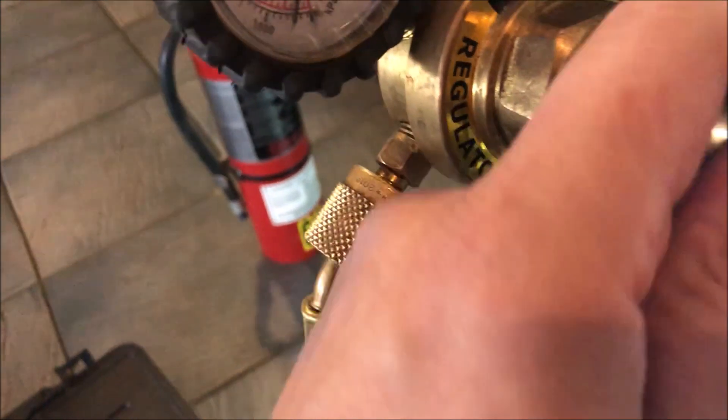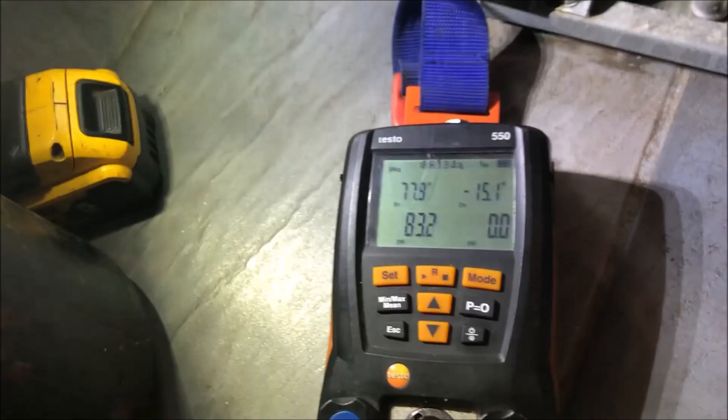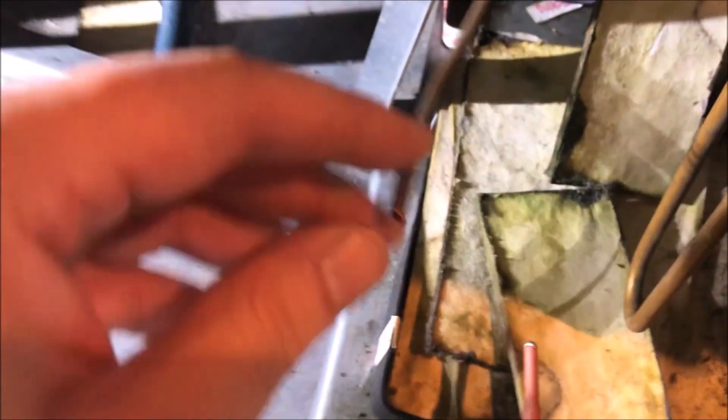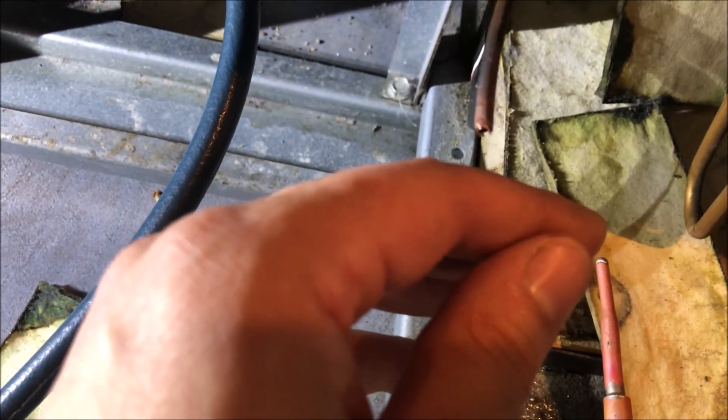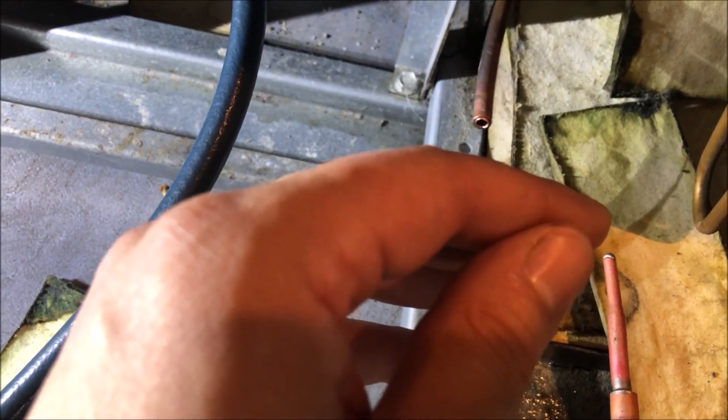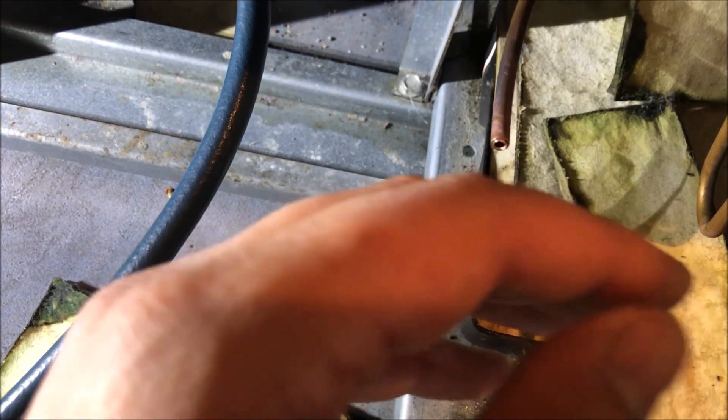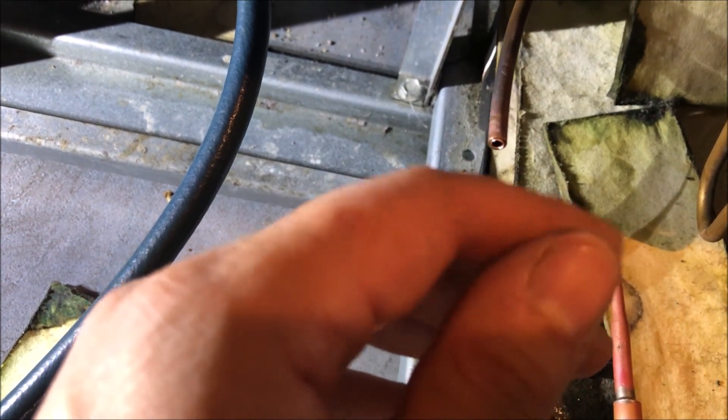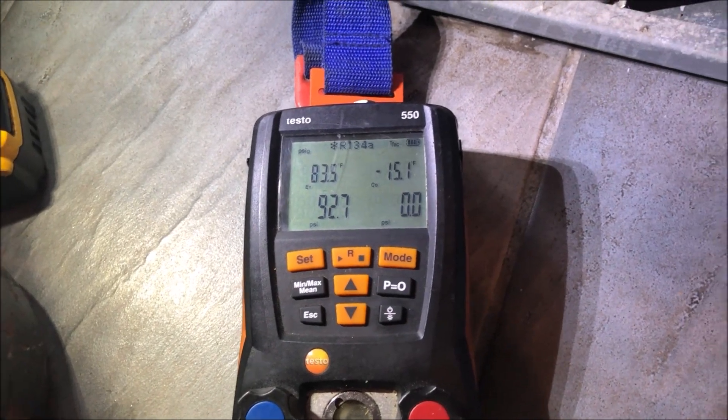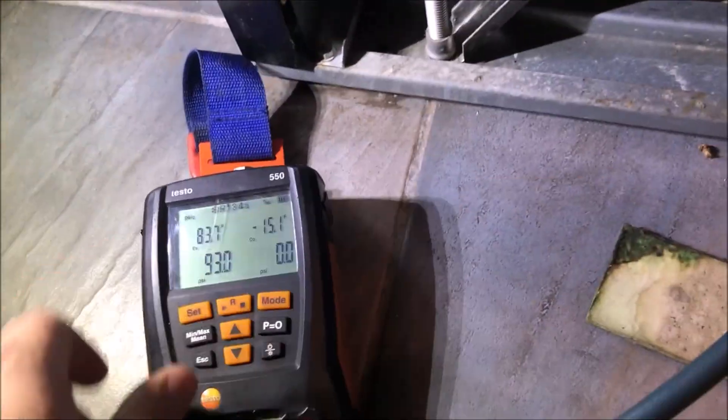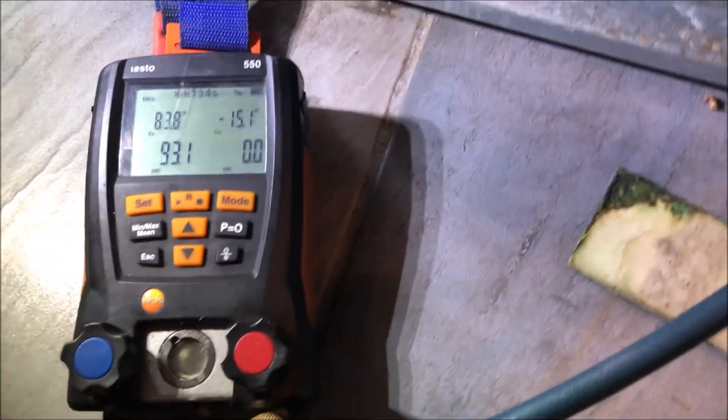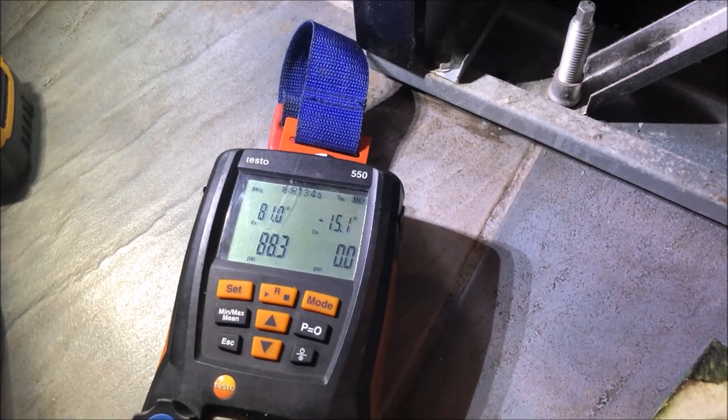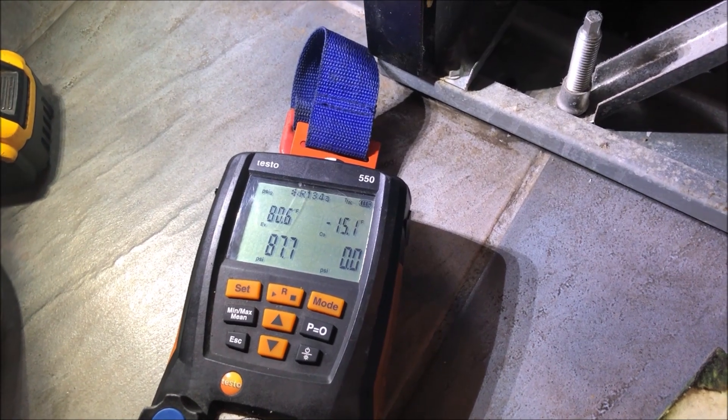So let's just keep pushing some nitrogen through. We're still not out of the woods here because what we want to do is we want to test the pressure coming through at our operating pressures. Just because we have it flowing through at 83 PSI right now doesn't mean that it's going to be flowing through where we're at our 14, 13, or 12 PSI. I'm going to continue to blow it through. Let's get a little bit higher here. We're up to 93. So what I'm going to do now is I'm going to shut off my nitrogen through the gauges and I want to test right around 14 PSI, make sure we have good flow.